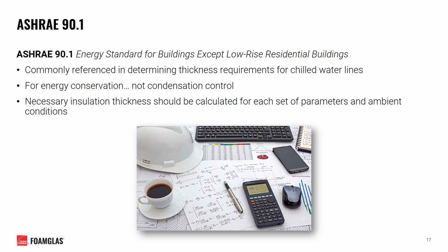Within the industry, there exist many different standards from different organizations to help aid in the design of commercial insulation systems. One such standard is ASHRAE 90.1, the energy standard for buildings except low-rise residential buildings. This standard is commonly referenced in determining thickness requirements for chilled water lines. However, it should be noted that this standard is built around energy conservation, not condensation control. In reality, necessary insulation thickness should be calculated for each set of parameters and ambient conditions that's unique to your system.